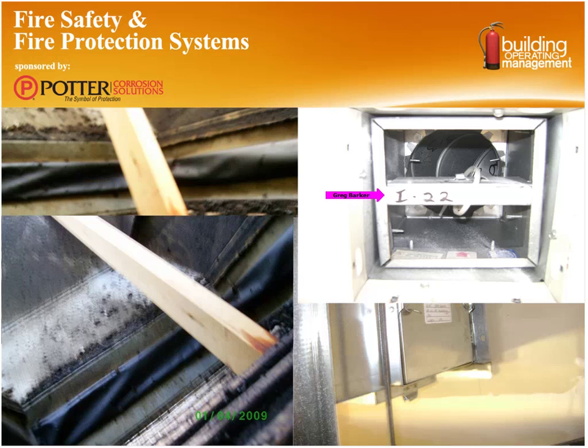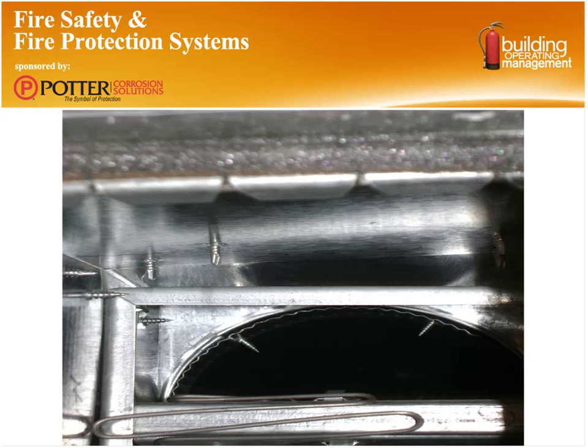If we take over here on this damper, you can see a zip tie put around that fire damper. It's not going to work very well with that zip tie in it. This picture over here is a picture of a typical access door. This one here, you really can't see it. These are photos from our technicians, and some of them are taken either with their small cameras or some of our flex cameras that we have. But this one in particular, the actual fire curtain damper in this duct is actually upside down. So unless the laws of gravity change, odds are that damper is never going to work in the event of a fire. It happens. That's what the inspection is there to prove.